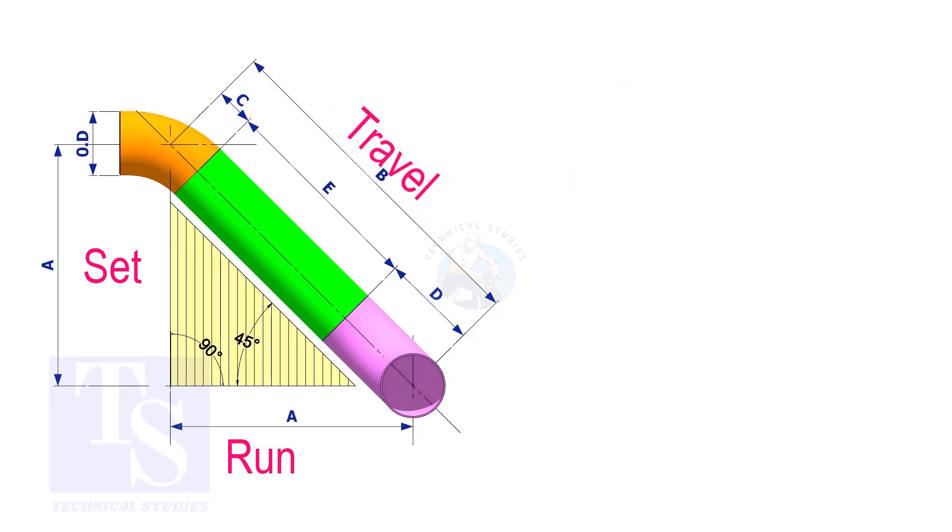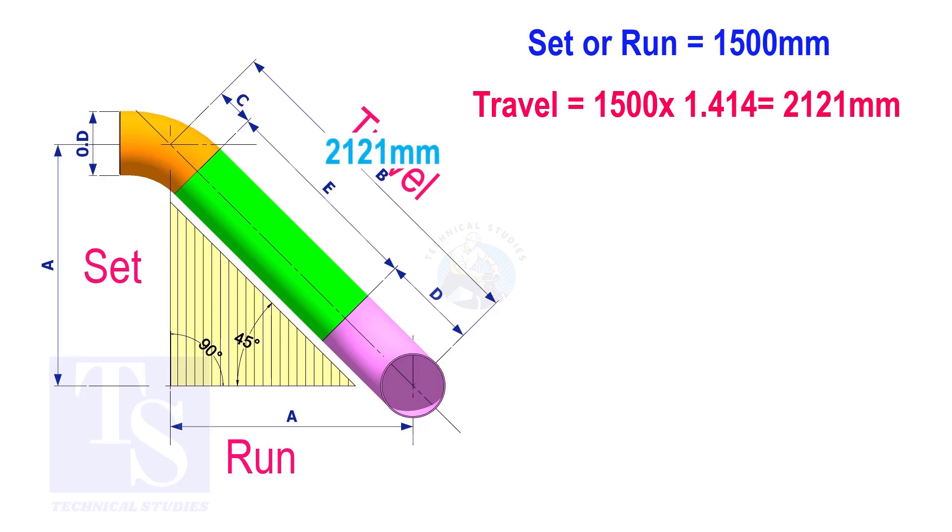Try another example. Suppose the value of the set or the run is 1500mm. The value of the travel will be 1500 multiplied by 1.414 equals 2121mm.